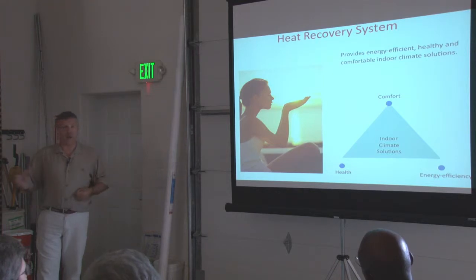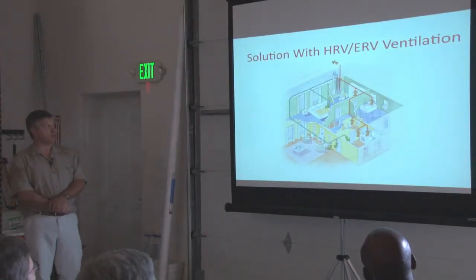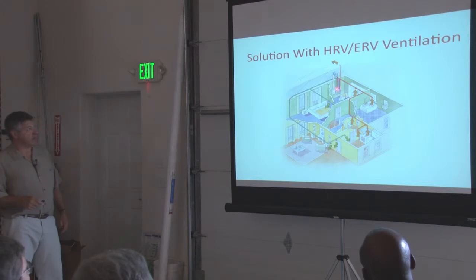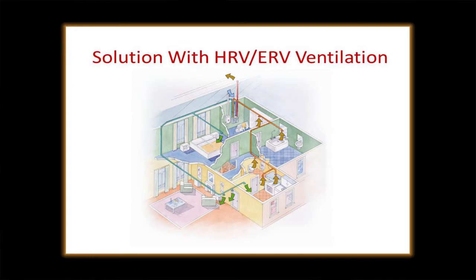Cool air being blown around the house can affect health as well. Our solution and our design principle for ventilation systems is to use a heat recovery ventilator with supply and return to the outside. Exhaust is coming out of bathrooms and the kitchen — those are all the red arrows. Supply is going into primarily bedrooms and living spaces, and that's balanced with the amount of supply into the bedrooms, living spaces, and returns out of the bathrooms and the kitchen. So you're getting rid of the moisture and poor quality air out of the bathrooms and kitchen. Our design focuses on bedrooms first and living spaces if necessary to balance the system.